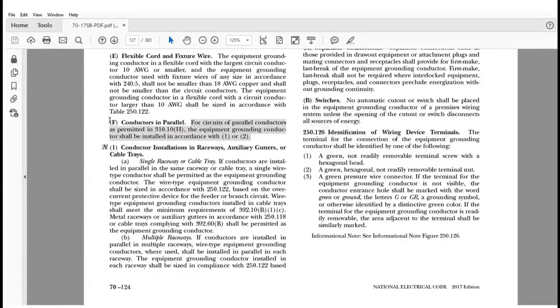Let's look at it right here. It says conductors in parallel. So we're dealing with when we have to run equipment grounding conductors in parallel. There have been problems through the years where you buy products like multi-conductor cables, like an MC cable, and you have a single cable which was never originally designed to be a parallel application. Yet it can be done, but the equipment grounding conductor inside that MC cable is only sized based on the overcurrent protective device that would be protecting the conductors in that cable. If you ran them in parallel, in accordance with 310.10 of the National Electrical Code, then they would be terminated together, connected together in parallel at both ends, to a larger overcurrent protective device than would have been intended for a single cable.